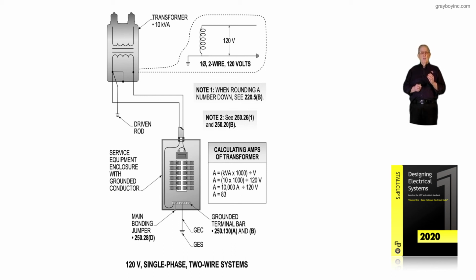And if the conductor rating, number 4, is 85 amps, you could move up to 90 amps to get the full benefit of the 85 amps. Or you could just round it down to an 80 amp overcurrent device and you completely protect that conductor's ampacity. So it's a choice. Which choice do you make that would give you the biggest benefit out of using that number 4 conductor? So this Figure 4-1 mainly just deals with taking a 120 volt single phase 2-wire service and determining, based upon the rating of the transformer, how many amps would be usable at the service equipment.